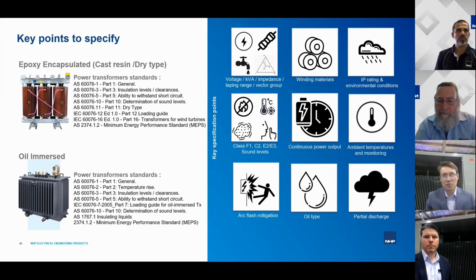However, there is an important difference we need to understand. Enclosed transformer versus a kiosk substation, where you can have a transformer along with other equipment such as HV switchgear and LV switchgear in one packaged kiosk. And this is where a different standard applies, such as 62271 part 202, and that dictates different requirements that actually allow derating of transformers within a kiosk. So the transformer doesn't have to deliver the full output. So that's a key difference we have to understand. But as far as we go, just a transformer on its own, it's always 100% regardless of enclosure.